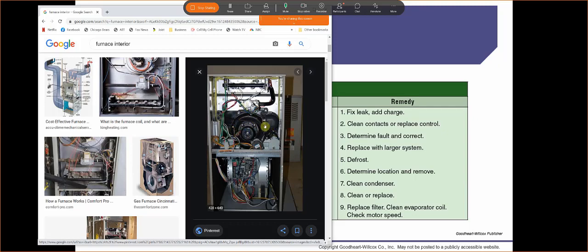So this thing is going to turn on first. Once it starts operating, the next step is going to be right over here. We're going to have a hot surface igniter. There may be a pilot that sits there if you have an older system, but most systems nowadays you're going to run into a hot surface igniter. This guy gets really hot. It's going to glow bright orange, and what ends up happening is, as soon as the gas is released, the flame is going to light.